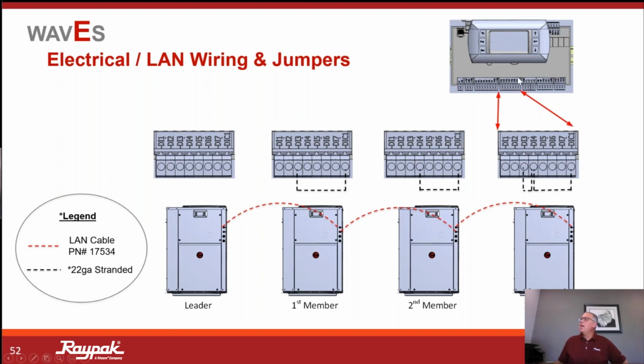If you were to take that cover off the front of the unit, right below the display, you're going to see all these little terminal blocks. They're very easy to identify. And we can stage, rotate and cascade up to 4 units. So the leader will not have anything going to it other than exiting. That LAN cable will then plug into the next unit. Then you'll put a jumper across DI3 and DIC1, and so on. This will feed the next unit, DI4 and DIC1, and then conversely, that last unit. Again, very easy to do.